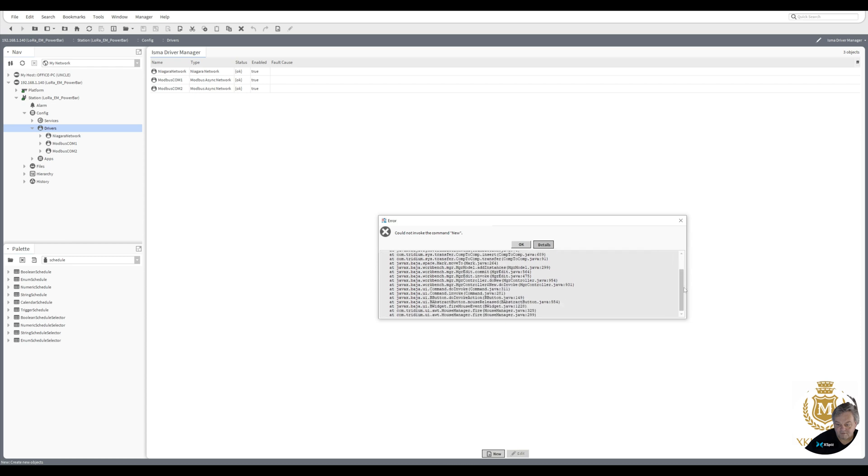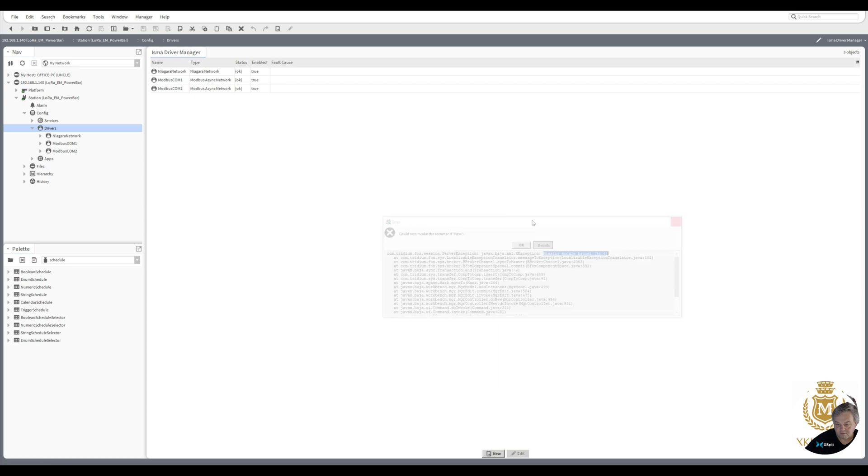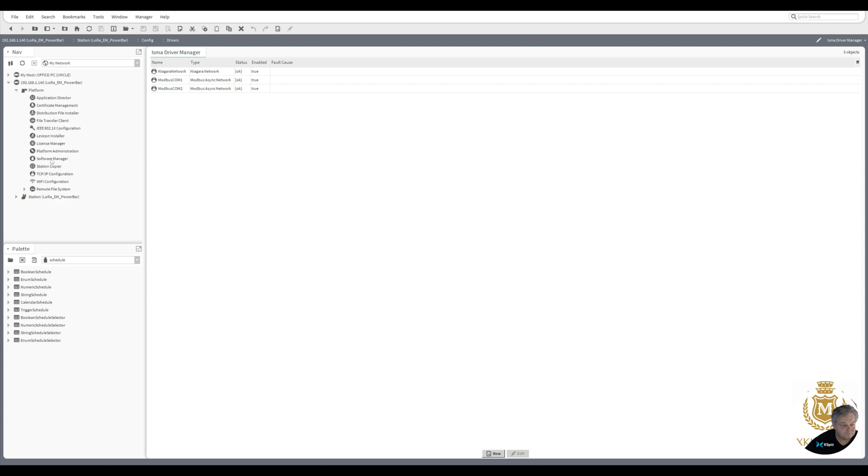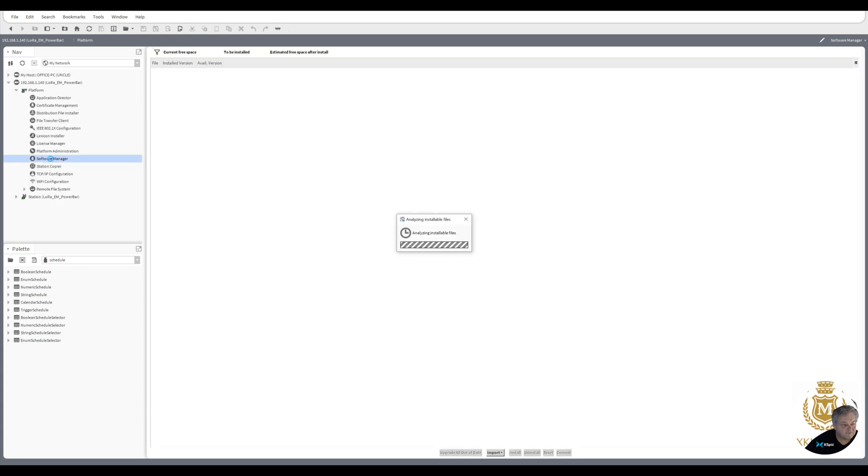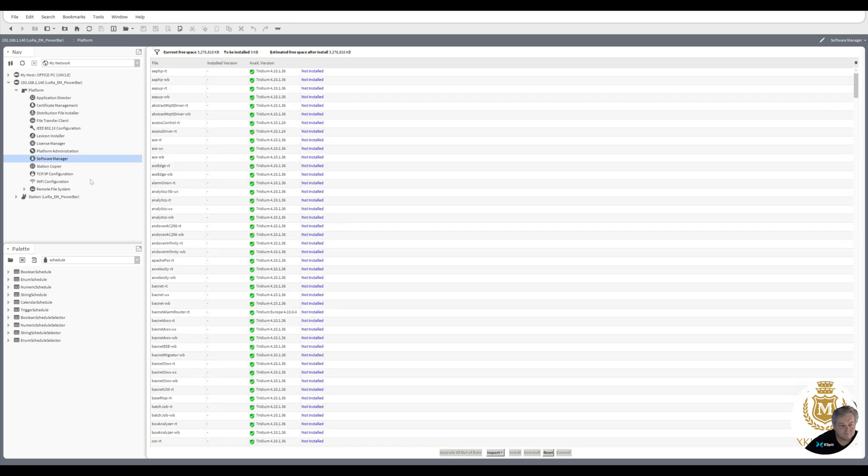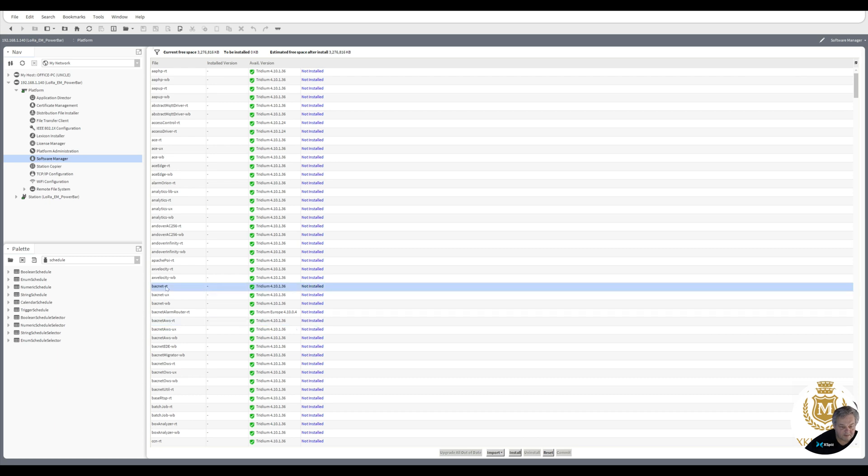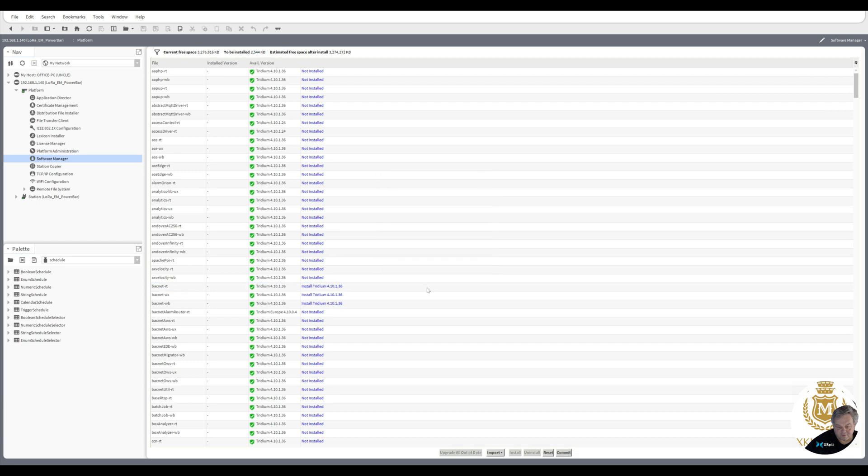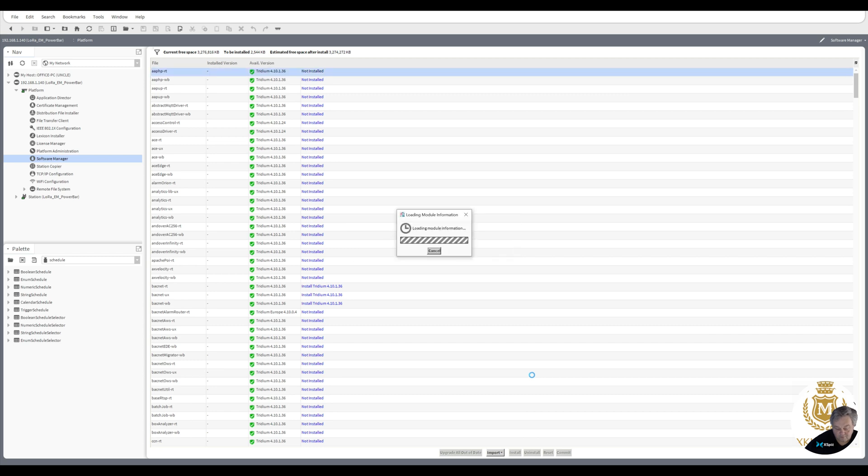This is what I wanted you to see. Now what we do is we go to services and we go down to software. Software manager. This is in the platform, platform software manager. We've got BACnet here. See, it's saying not installed. So you only need to click one of them and it will install the other two. A popup there saying install the other two, and then commit to that. That will install it. Sometimes it needs to do a reboot, sometimes it doesn't.